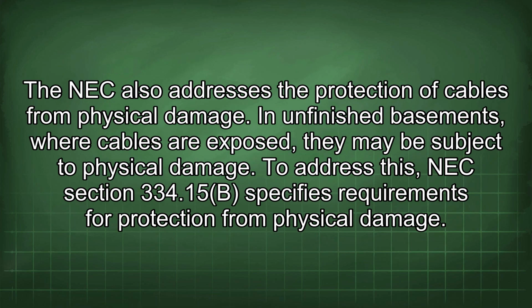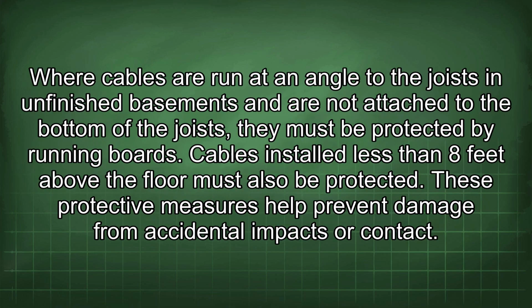The NEC also addresses the protection of cables from physical damage. In unfinished basements, where cables are exposed, they may be subject to physical damage. To address this, NEC Section 334.15b specifies requirements for protection from physical damage. Where cables are run at an angle to the joists in unfinished basements and are not attached to the bottom of the joists, they must be protected by running boards. Cables installed less than 8 feet above the floor must also be protected. These protective measures help prevent damage from accidental impacts or contact.